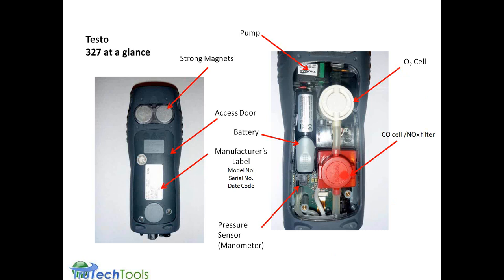The CO sensor is also replaceable. They're also covered by the 3-year warranty on both the O2 and the CO sensor. The CO sensor has a NOx filter built in. It's a bit like a bayonet cartridge in the top of the meter, and I think we have a photograph of that in a second to show you what it looks like when it comes apart.